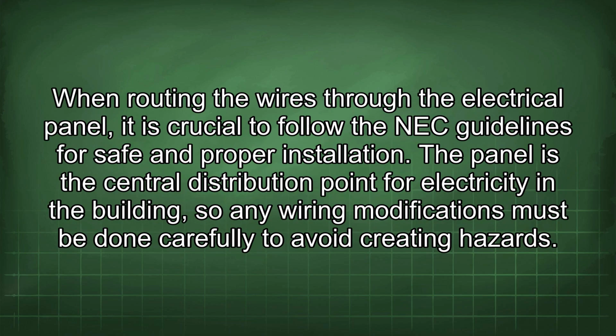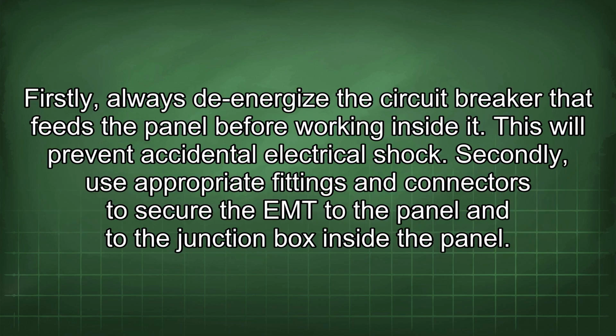When routing the wires through the electrical panel, it is crucial to follow the NEC guidelines for safe and proper installation. The panel is the central distribution point for electricity in the building, so any wiring modifications must be done carefully to avoid creating hazards. Firstly, always de-energize the circuit breaker that feeds the panel before working inside it. This will prevent accidental electrical shock.